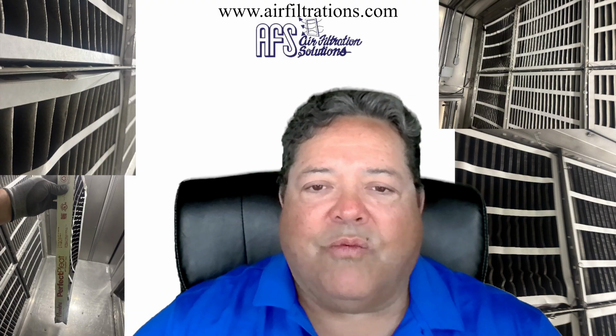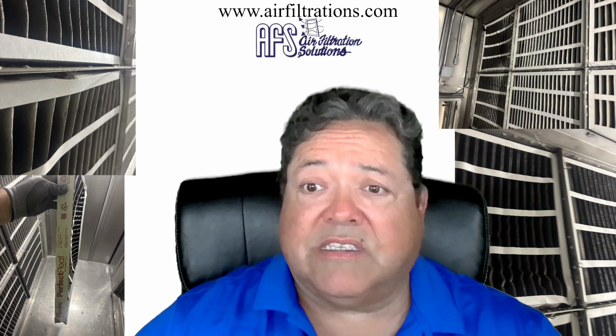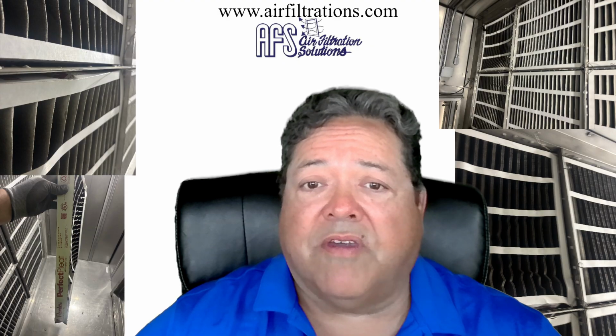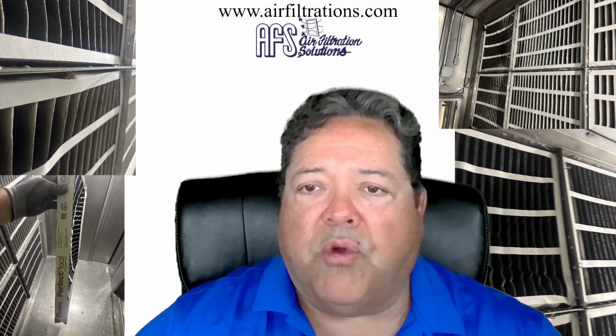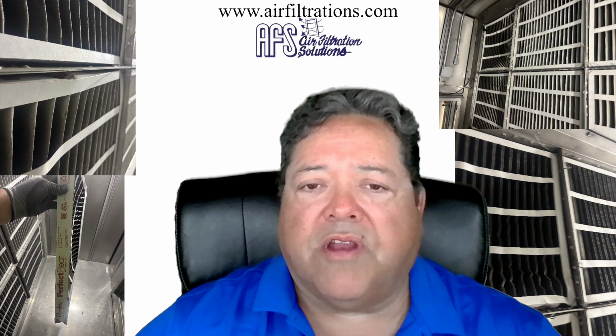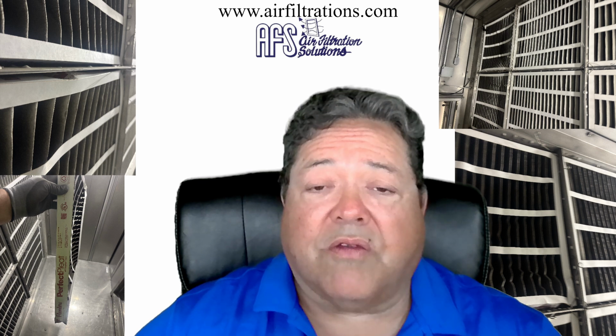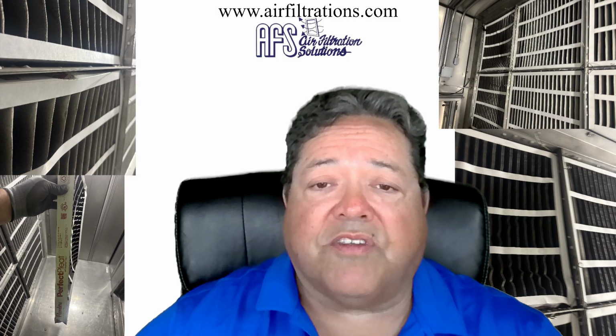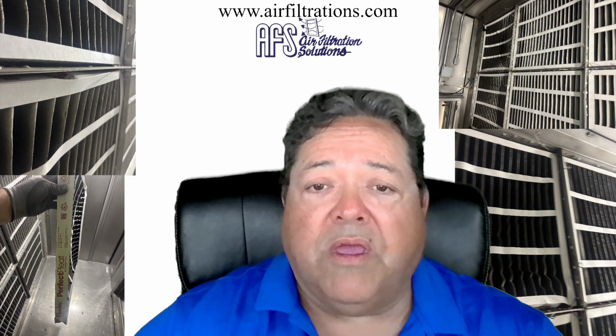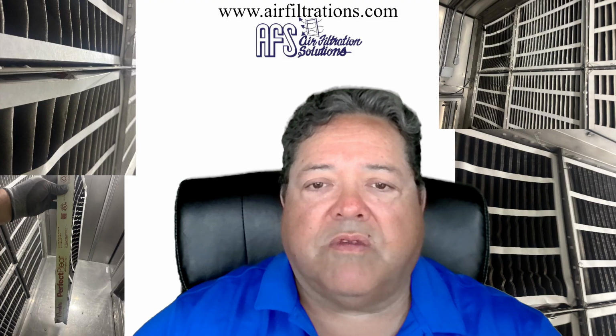Because again, we have seen air handlers with pleated filters in place for not even a month, which is the case right here, and you already see signs of structural fatigue. They just can't withstand the moisture in the air. Then you combine a pretty good airflow, and you see signs of buckling. Probably in another week or so, you would have had collapsing and then dirty coils, which is what this facility did not want. So we went in there, we put our panels in, and let me show you the results.